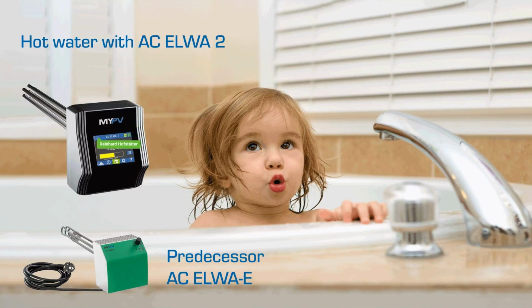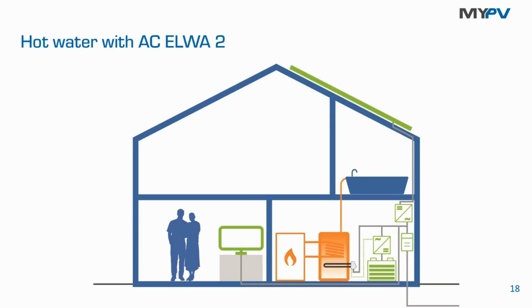And AC ELWA 2 is a newer generation of a product named AC ELWA-E. It's on the market for approximately half a year now. And here I would like to explain why it is so essential to control the thermal power output linearly. Because in a residential building or in an on-grid PV system, there are two things that are changing permanently. Number one is the PV output. It's clear why this is changing. The clouds are moving on the sky and the irradiation from the sun is not constant. The other thing that is changing permanently is the demand of power in the building. So the electric loads, something is always switched on and off and on and off.